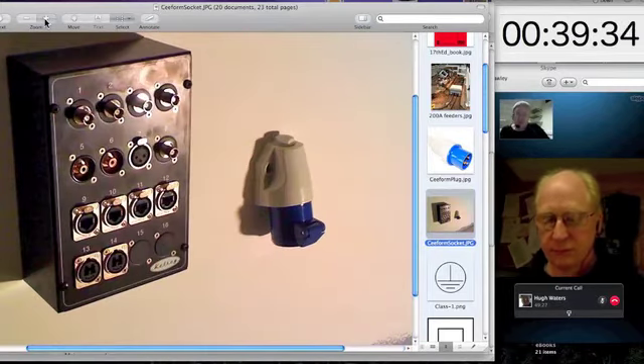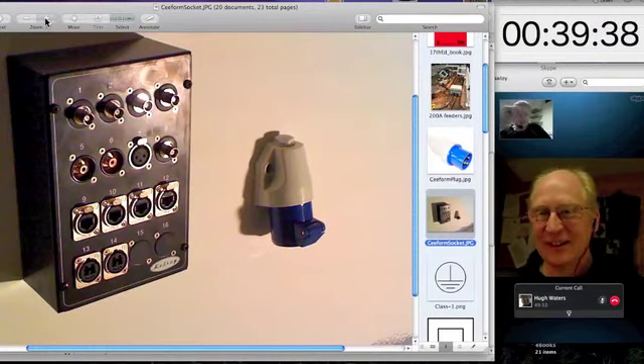And in fact, you mentioned that 1-inch machine that you had to deal with. I was called back to a facility that we'd built, a year or so after we'd finished building it, and they had hum over all their analog feeds. You couldn't look at an analog picture without seeing hum bars on it. And for 2 days, I tried to discover what was causing this. Of course, because mains is mains, you can't even take a voltmeter and go around measuring where the hum's been induced, because it's on everything, and the impedances back to earth are so tiny that there's no way of getting a relative feel about where it is being induced.